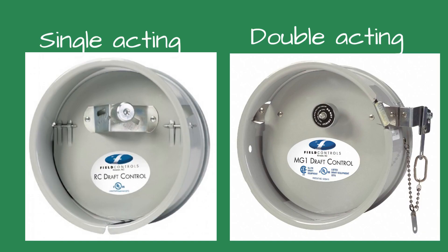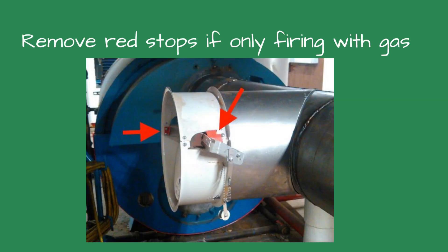Each fuel or combination of fuels requires a specific type of barometric damper. Single-acting is traditionally used for oil-fired burners, while double-acting is used for gas or dual-fuel burners. The red stops found in double-acting dampers should be removed if only firing with natural gas.